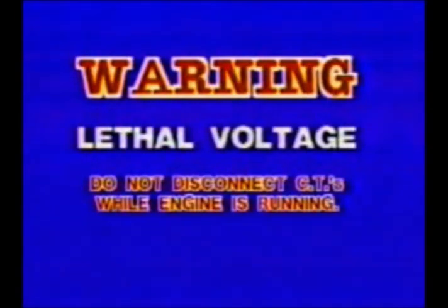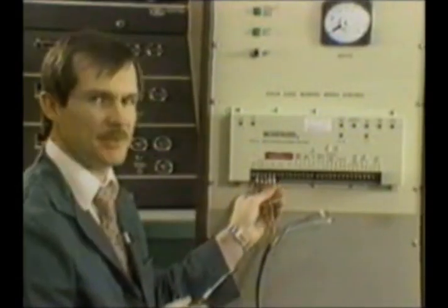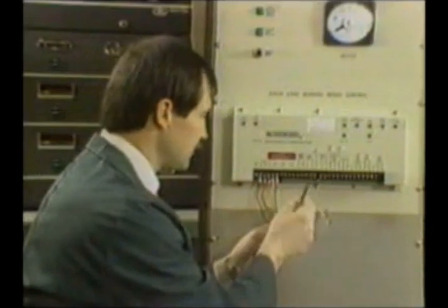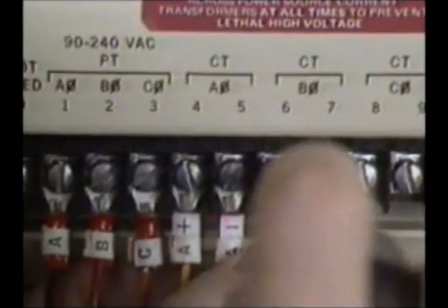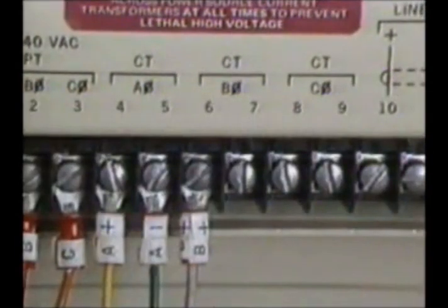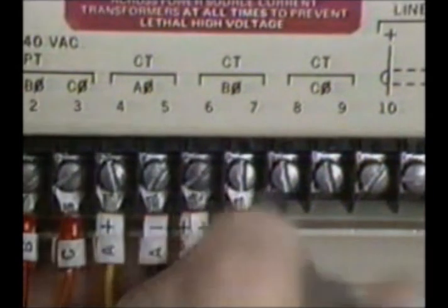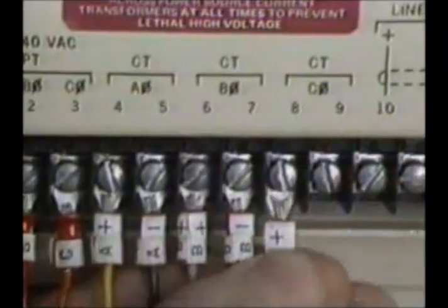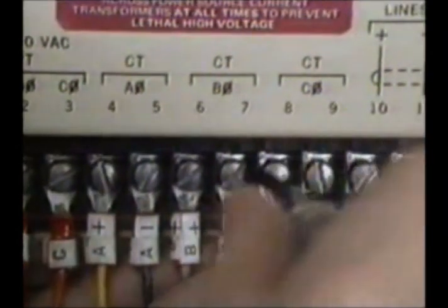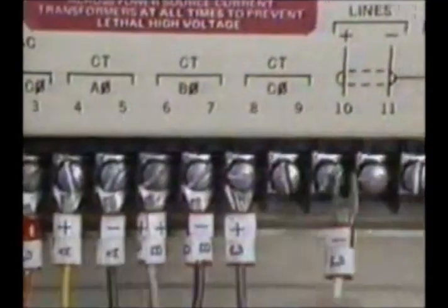Also, your CTs, you can have a lethal voltage across your CTs if you have one side disconnected from your terminal block when you're loading the engine. So you want to make sure both of your CTs are connected up before you start the engine and run. Of course, we have phase A, B, and C CTs, and later on in the demonstration I'll show you how to check to make sure you have your CTs and PTs hooked up correctly, and if you don't, I'll tell you how to find which ones are hooked up incorrectly and get them straightened out.